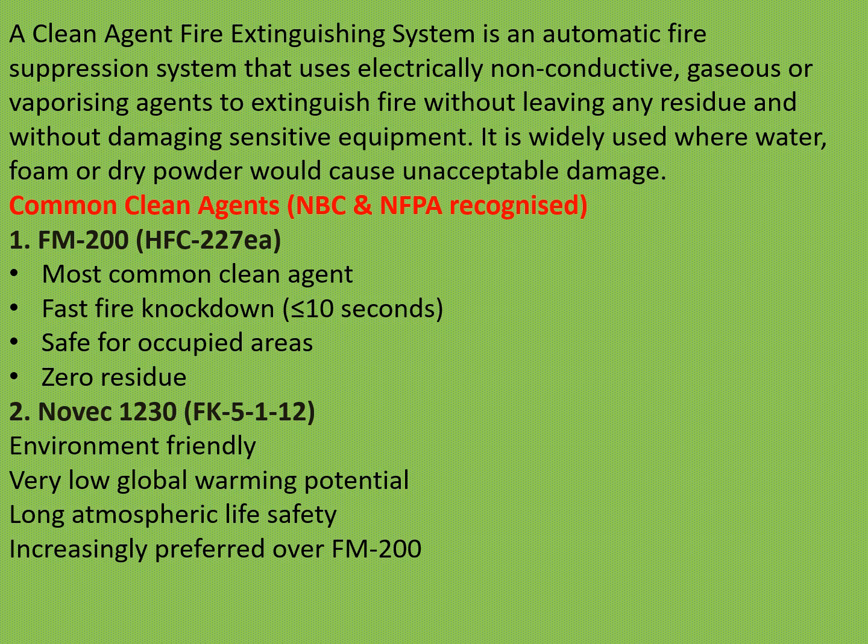A clean agent fire extinguishing system is an automatic fire suppression system that uses electrically non-conductive gaseous or vaporizing agent to extinguish the fire without leaving any residue and without damaging sensitive equipment. It is widely used where water, foam or dry powder would cause unacceptable damage.